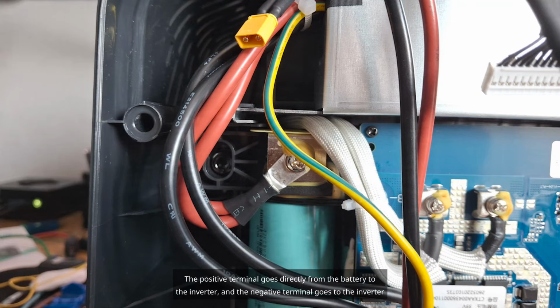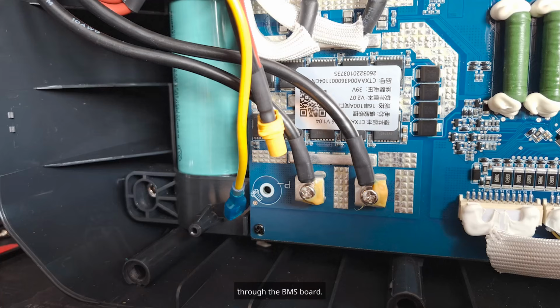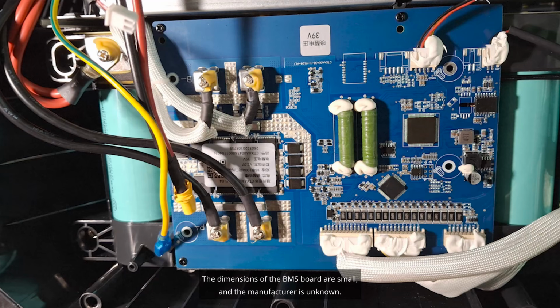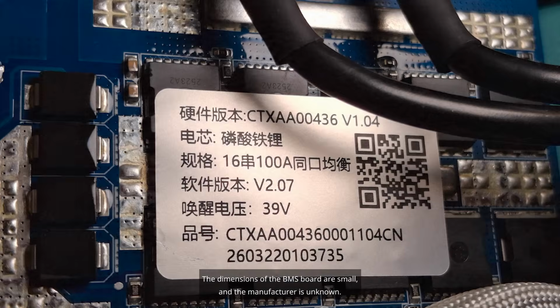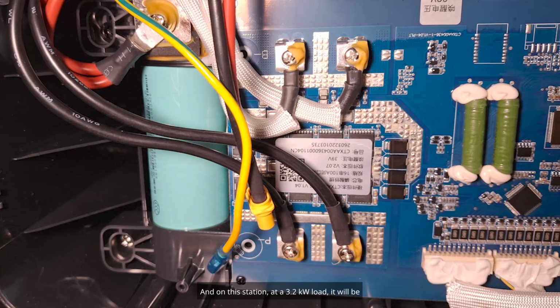The positive terminal goes directly from the battery to the inverter, and the negative terminal goes to the inverter through the BMS board. The dimensions of the BMS board are small, and the manufacturer is unknown. It's rated for a current of up to 100 amps, and on this station at a 3.2 kilowatt load it will draw a current of around 60 amps from the battery, so there's a safety margin.